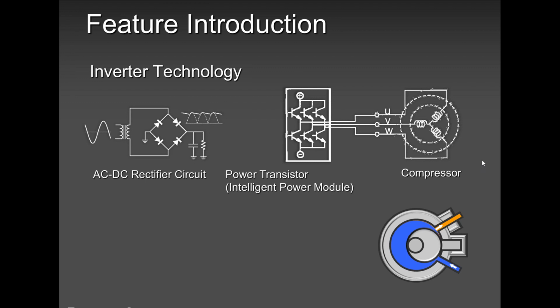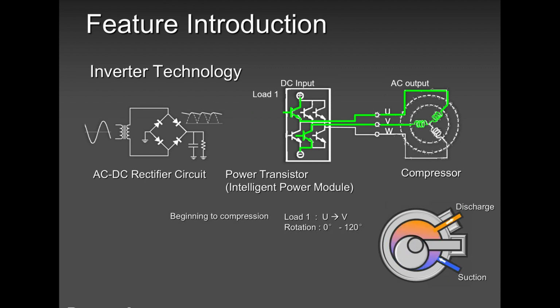Many guys are calling me and asking me if it was DC or AC. Oh, why is it a DC compressor then? Yes, it is a digitally controlled brushless compressor, but the windings need AC volts, not DC volts. To regulate the frequency, you need AC volts. You cannot regulate by using DC volts. So always remember, use your meter by measuring AC volts here, and it has to be balanced. It has to be balanced. If you're not getting balanced voltage, you will have a problem that I will explain to you in the next few slides.